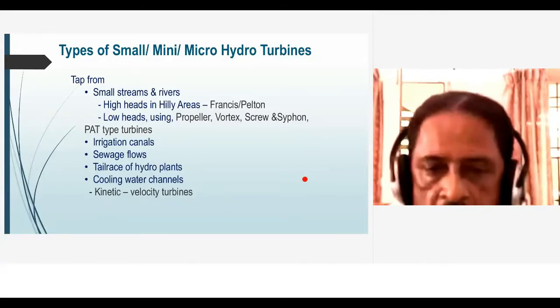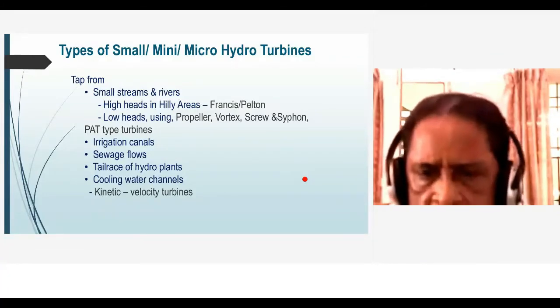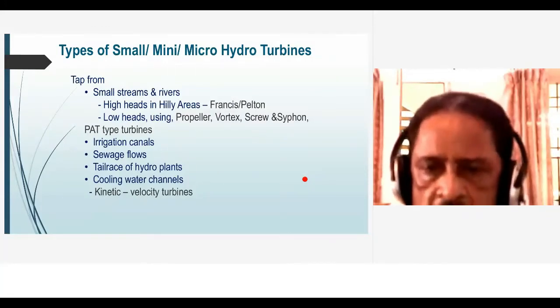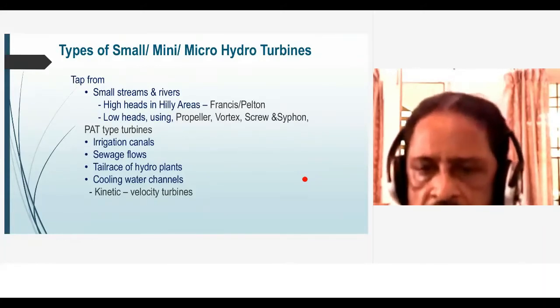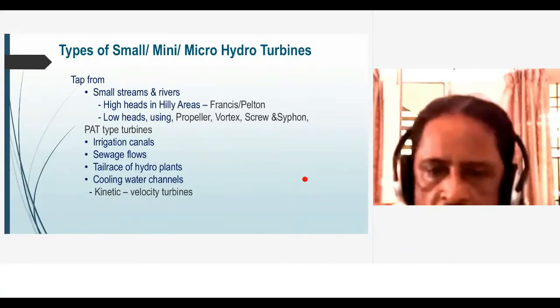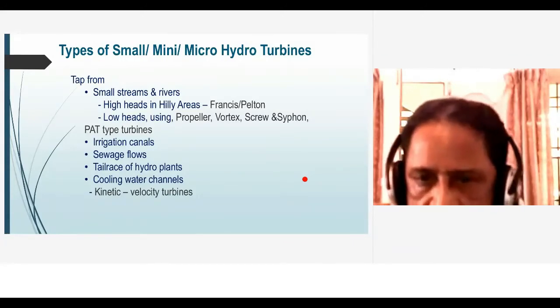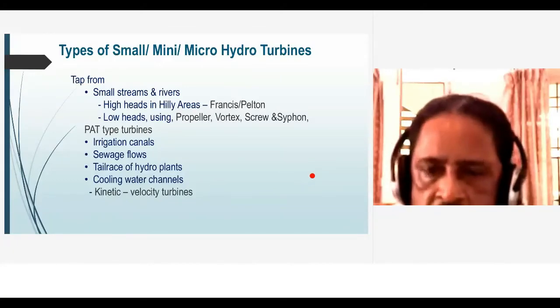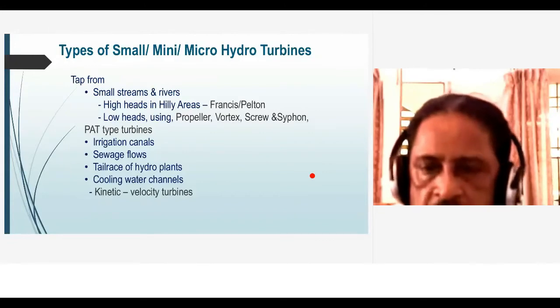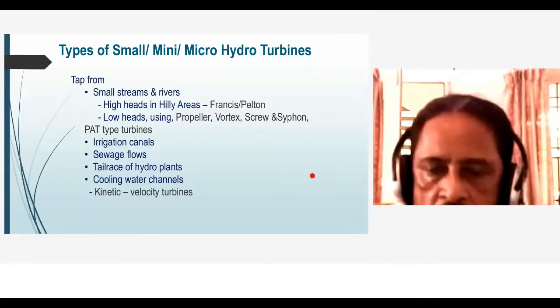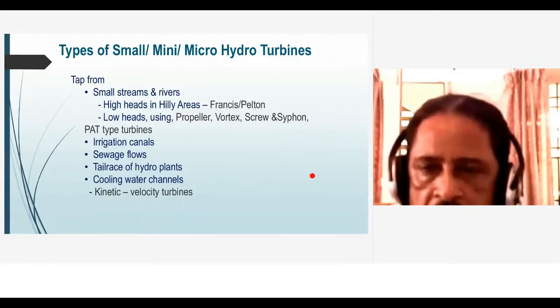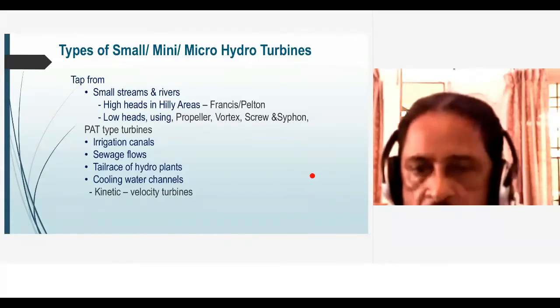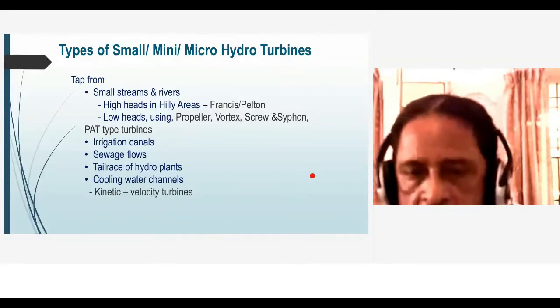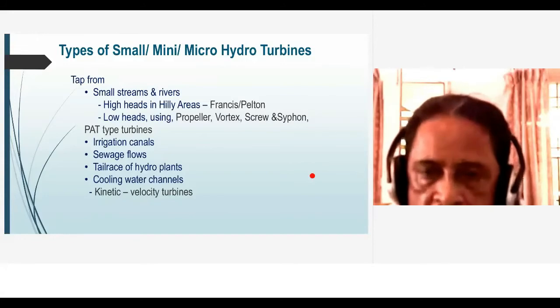For hilly, high head areas, you can use Francis and Pelton turbines. For low heads, I'm coming to mini and micro turbines - propeller turbines. The Kaplan turbine is actually a propeller turbine. Propeller turbines have no control over the gate vanes or blades. A semi-Kaplan has movement for either the runner blades or the gate vanes, while a full Kaplan has movement for both runner blades and gate vanes.